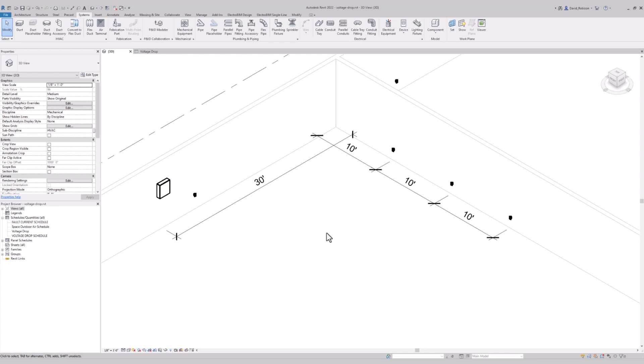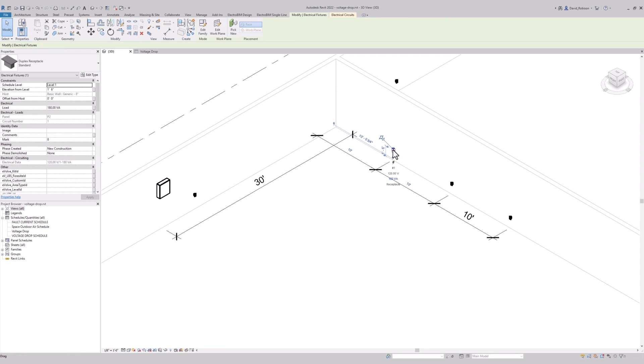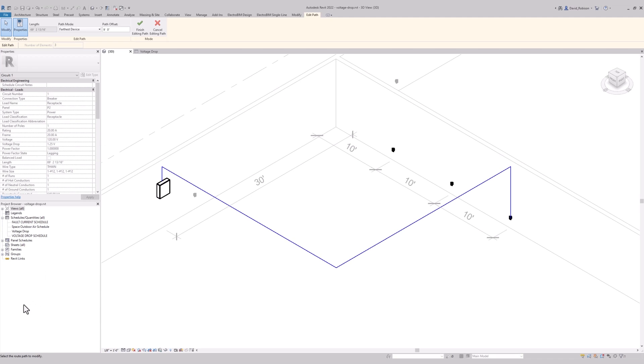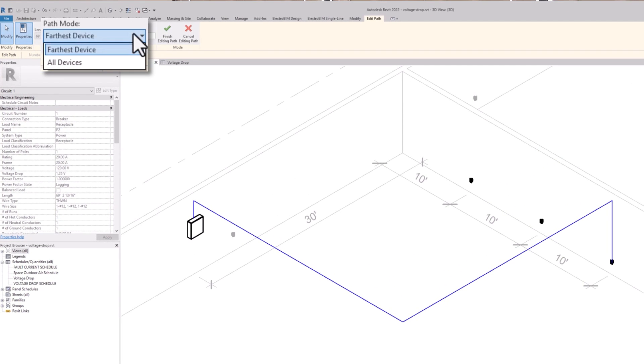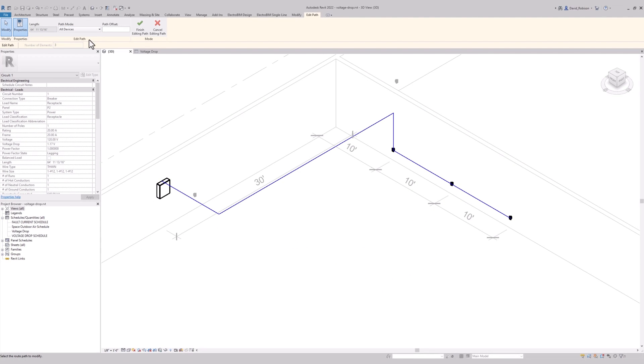Next, we have the length on the circuit. This is where Revit actually should be able to add a whole lot of value because it knows where all of these devices are in three-dimensional space. Revit has the concept of a circuit path it uses to calculate this length. If you select the device and select the circuit, you can press Edit Path and see what that path looks like — the blue line running from the farthest receptacle to the panel. Revit also has an option to change the path mode from farthest device to all devices, and there are options for modifying this path if you want to account for a different length.